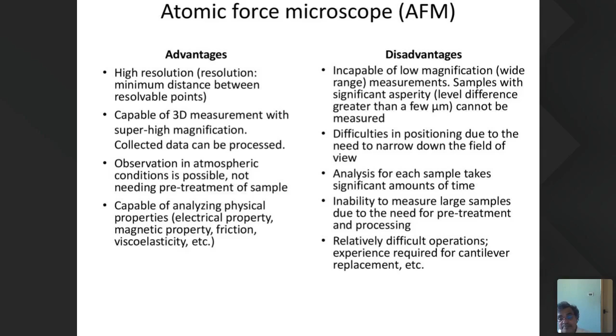Difficulties in positioning due to the need to narrow down the field of view. Analysis for each sample takes a significant amount of time. Inability to measure large samples due to the need for pre-treatment and processing. Operation is relatively difficult. You need a trained, experienced operator, especially for the spare replacement, etc.